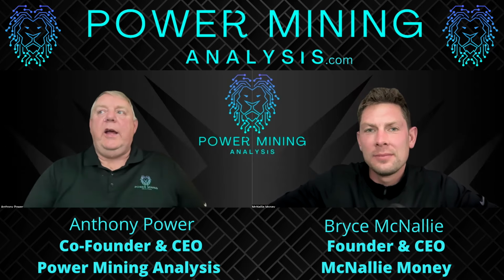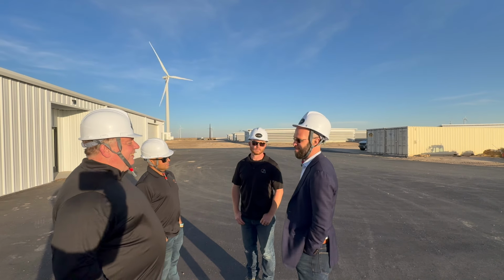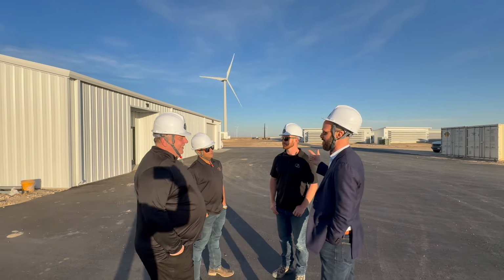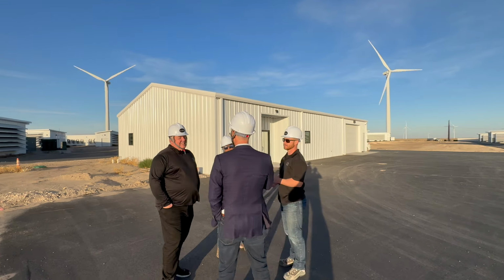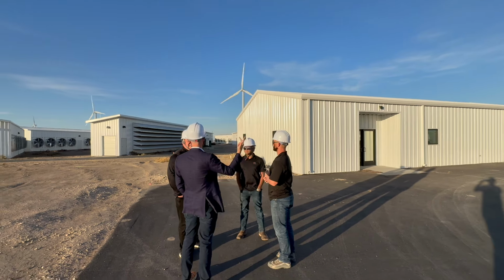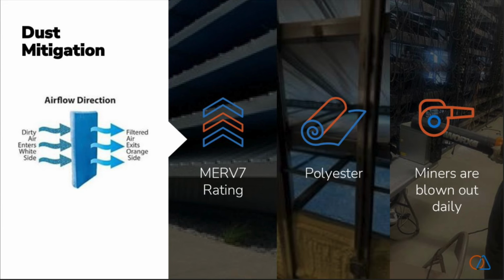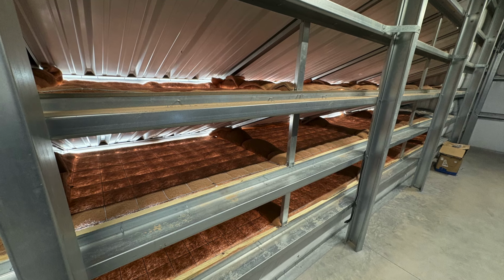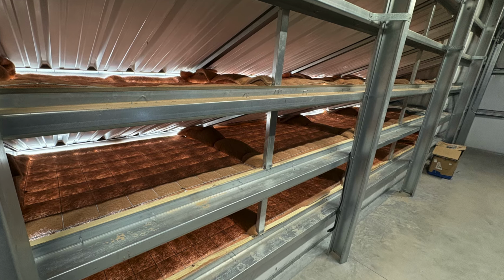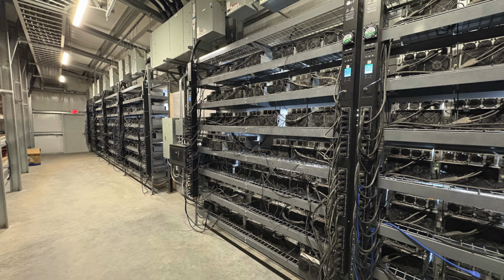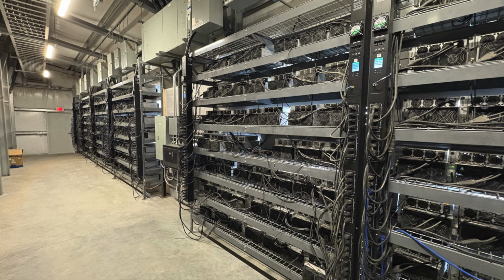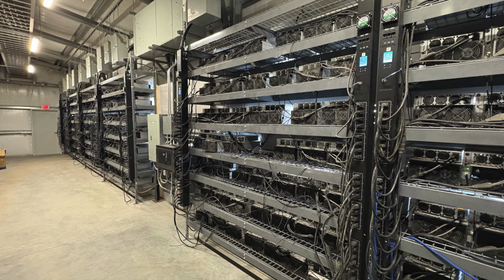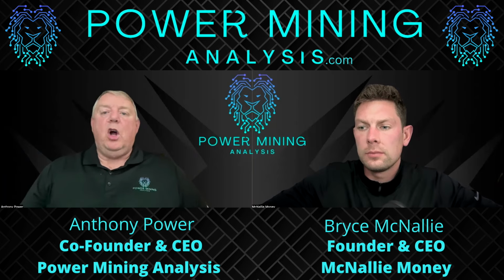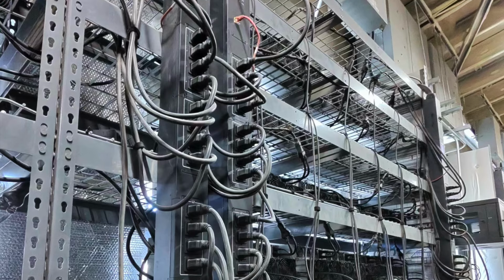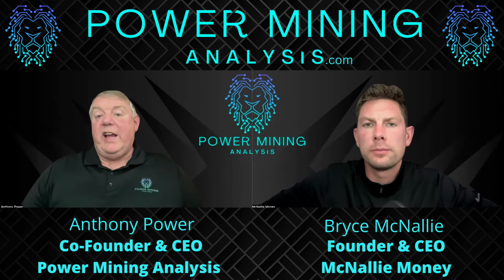But joking aside, it looks like they've really got significant design there. It gives them a competitive advantage against peers because they've really looked into the airflow, and you could tell from the external and internal how the system was working with the filters and the spacing. The spacing was really important because as air comes through, if any dust particles aren't picked up by the filters, they're likely to fall in the first 1 to 2 feet from coming through the actual ducts. They have something like a 6 to 7 feet gap between the wall of the infrastructure and the mining machines themselves. So worst case scenario, if any dust does get through the filters - and these filters are blown every day and changed every quarter - there are controls in place to make sure the PDUs don't start having dust entering their systems.